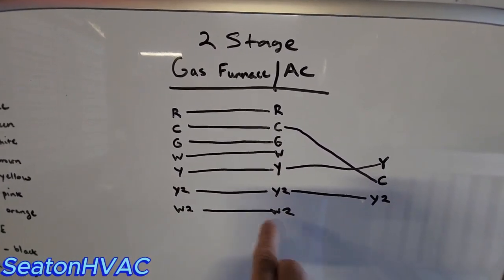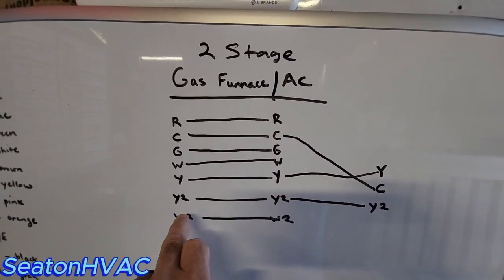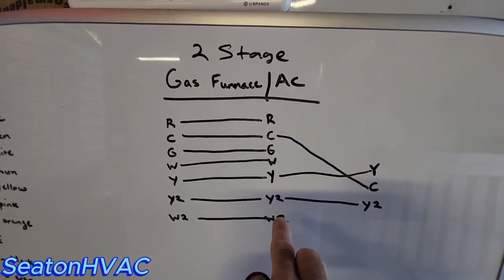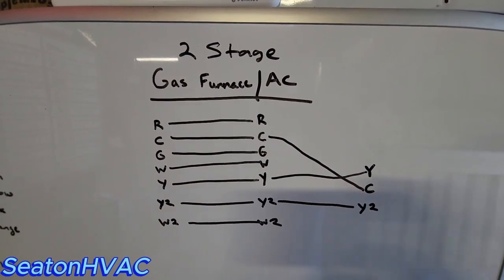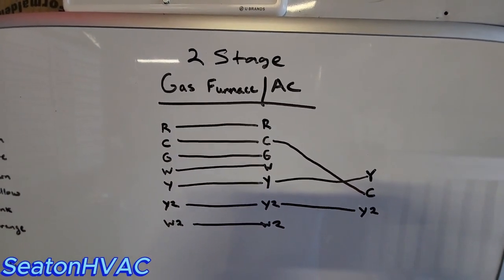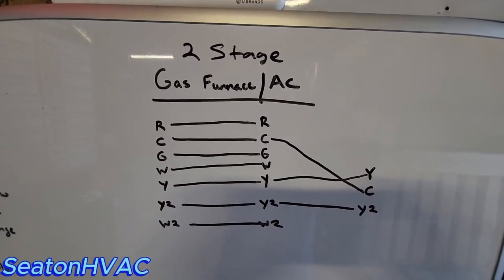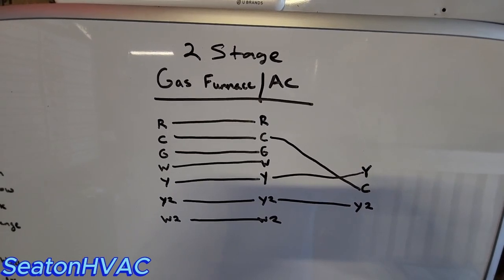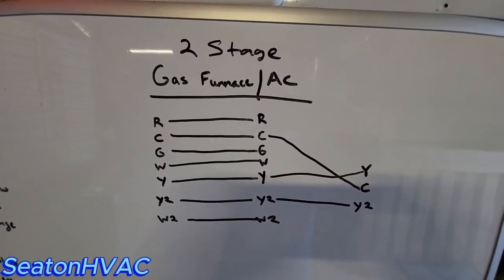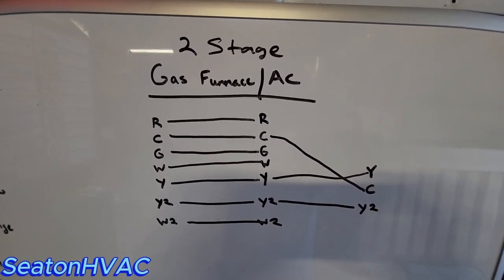And then your W2, your brown wire, just goes from your thermostat to your furnace, obviously, because that's for your heat. It's not going to go out to your AC. So that's a quick two-stage gas furnace AC. Let's do a single-stage heat pump with one source of backup heat. Let me show you how that works.